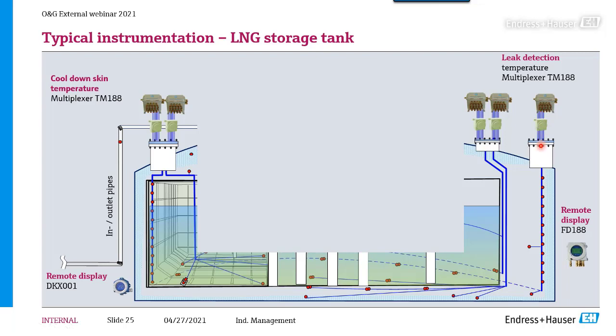Something similar happens with leak detection, where we have vertical sensors. Normally they provide a vertical linear temperature profile, but it's also not unusual to have three-dimensional temperature measurement on the outer shell, where we fix some skin points exactly on the surface of the wall, to detect any decrease in temperature which tells the customer: be careful, there might be a leakage.